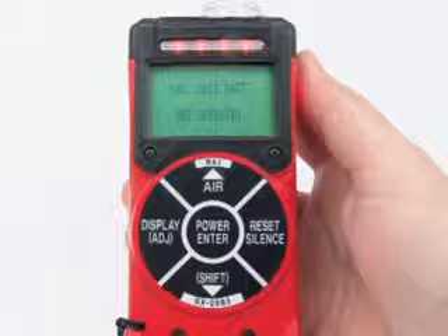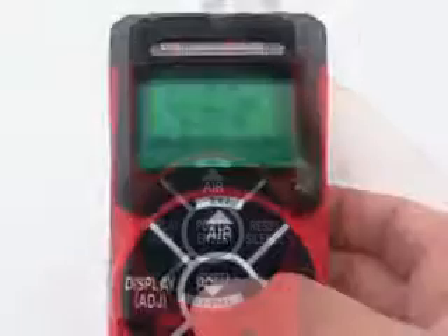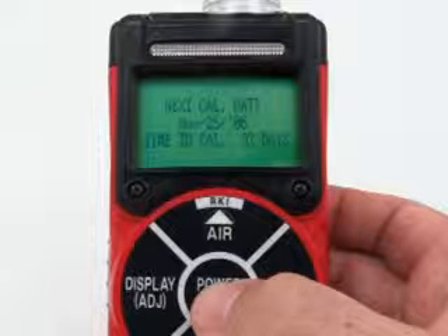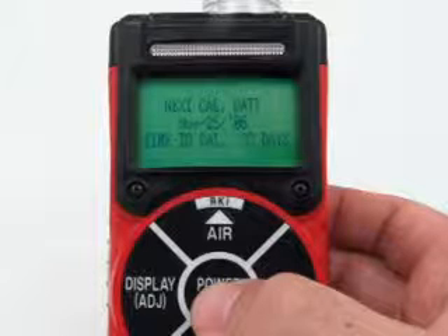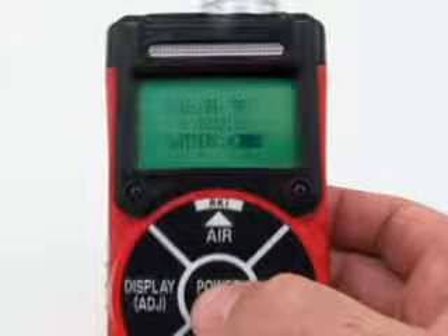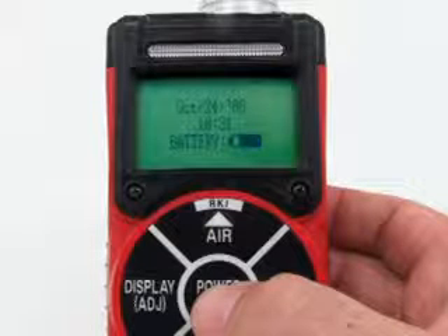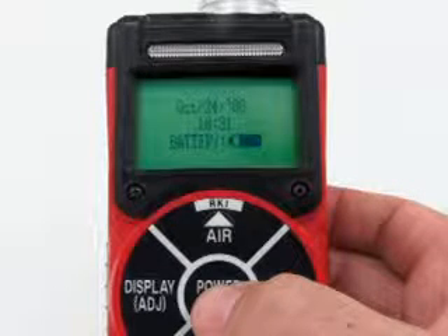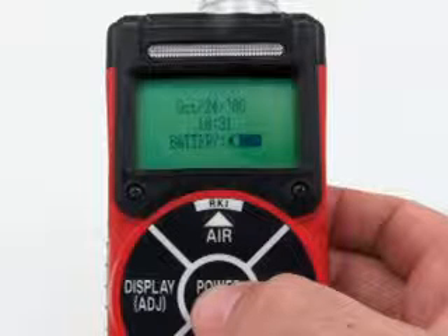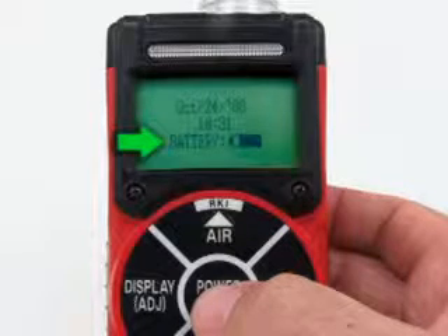If the unit is due for calibration and cal expired action is set to Cannot Use, then the GX2003 cannot be used until a calibration has been performed by selecting Auto Calibration in the Setup Mode menu. If calibration is not due or cal expired action is set to No Effect, then a screen appears for a few seconds indicating when the next calibration is due. Next, the date, time, battery level screen appears for a few seconds. This screen displays the current date, time, and an indication of how much battery charge remains.